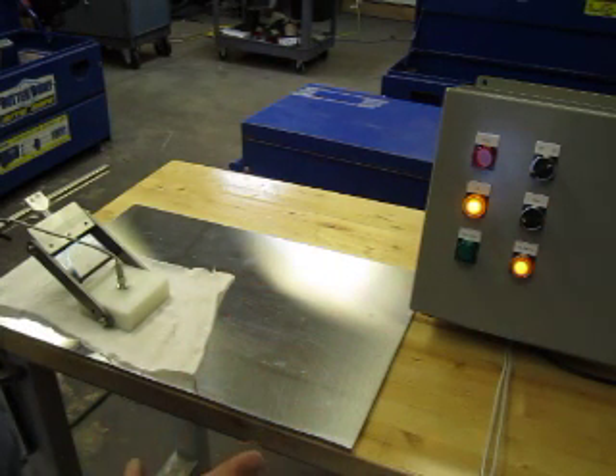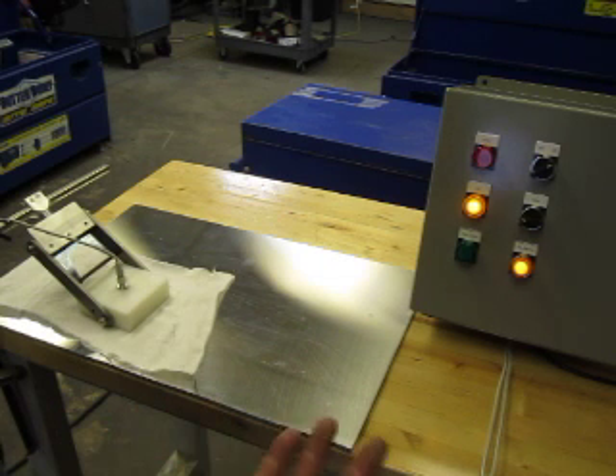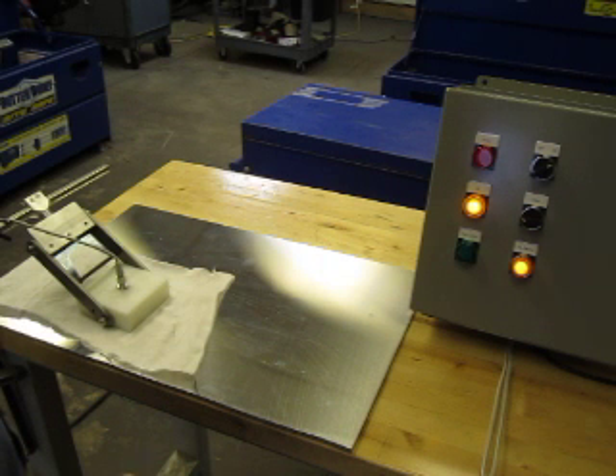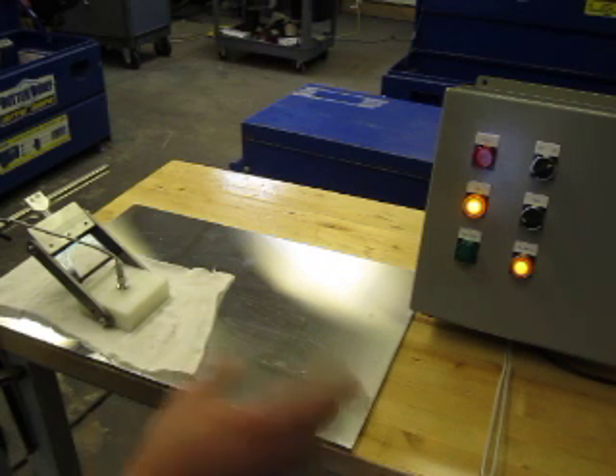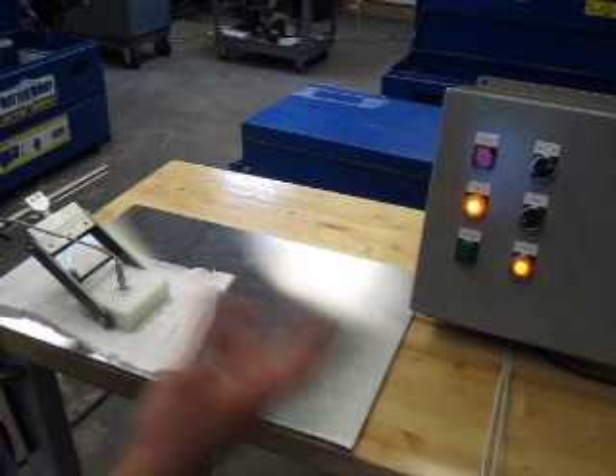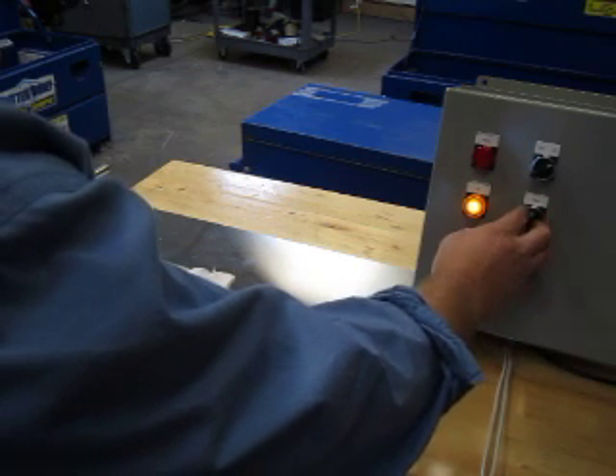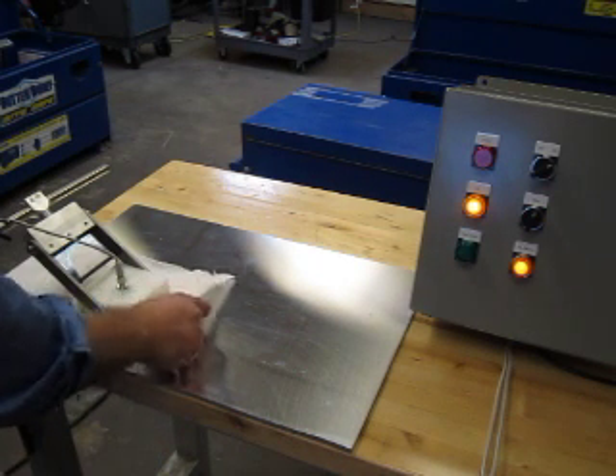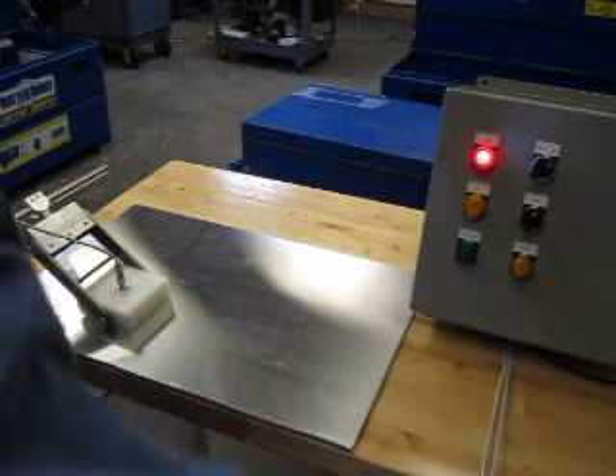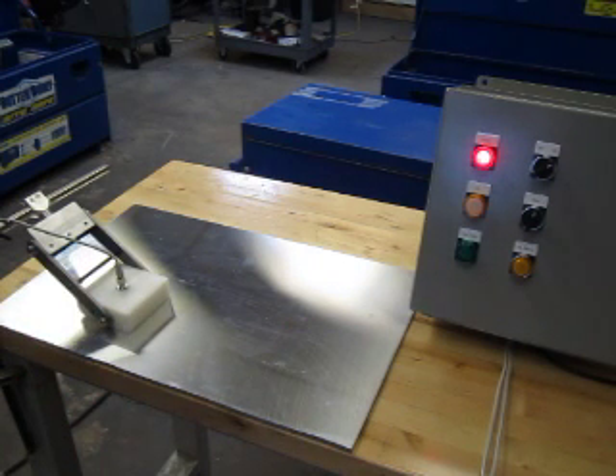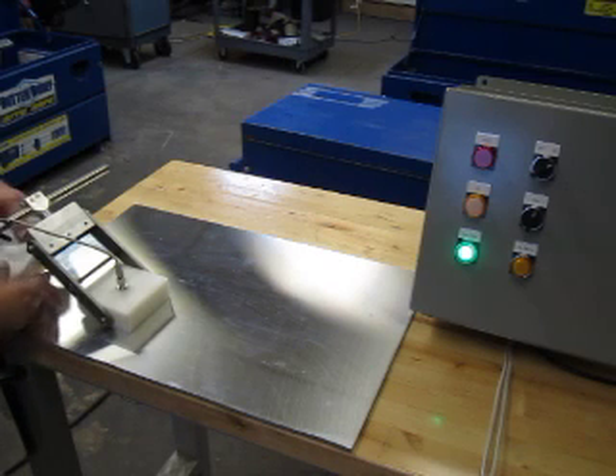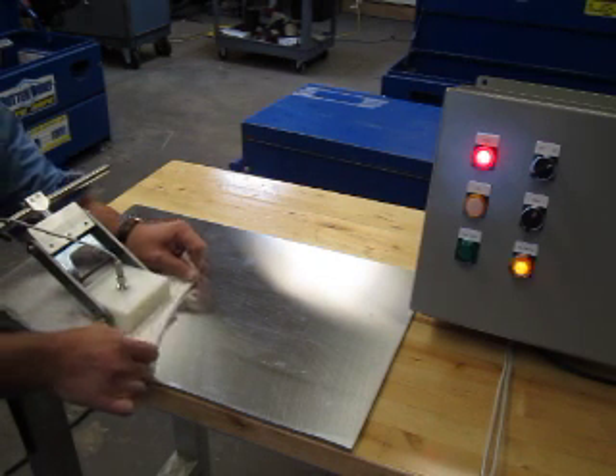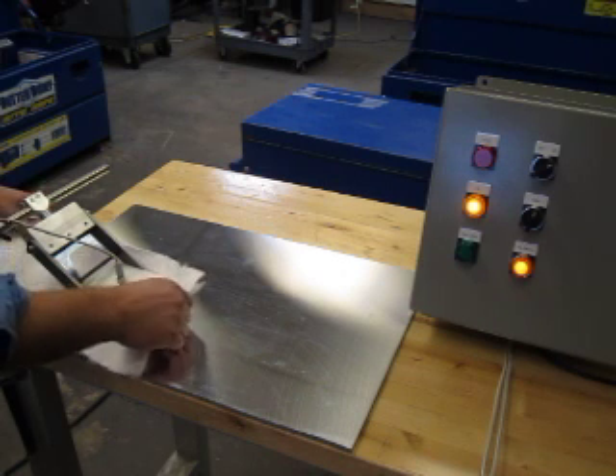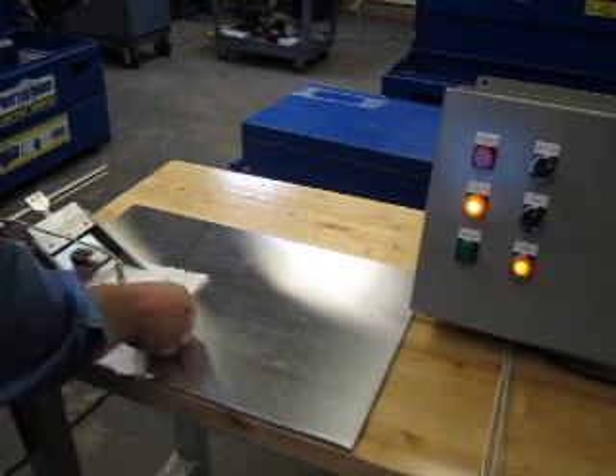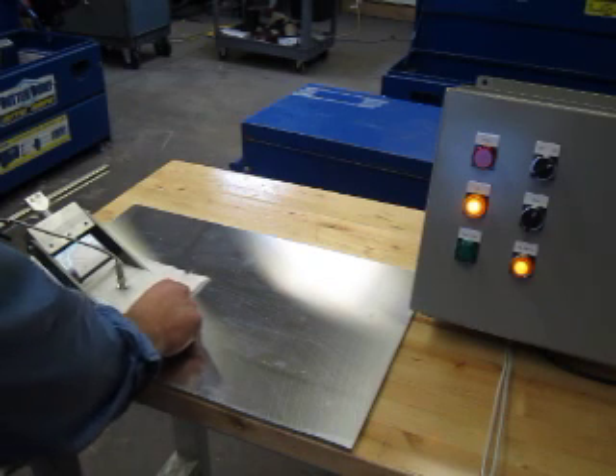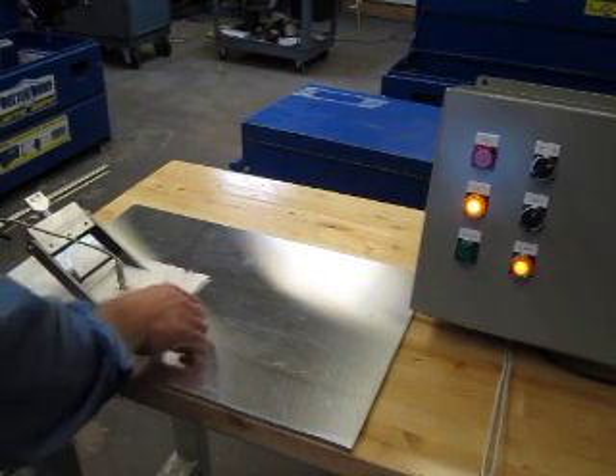So that's something that you're just going to have to play with while it's running to see if we can get a stable system that continues to run when there's no seams but catches every seam that goes through. So it does catch it pretty quick, and you can see it stays on for 3 seconds. Even though that seam whipped by there in a couple of milliseconds, we still hold that relay and that light on for 3 seconds no matter what.